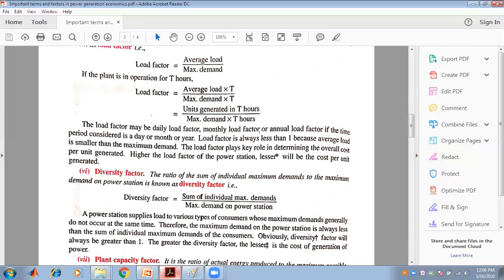The diversity factor is the ratio of the sum of individual maximum demands to the maximum demand on the power station. The power station supplies load to various types of consumers whose maximum demands generally do not occur at the same time. Therefore, the maximum demand on the power station is always less than the sum of individual maximum demands. The diversity factor will be greater than 1. The greater the diversity factor, the lesser is the cost of generation of power.